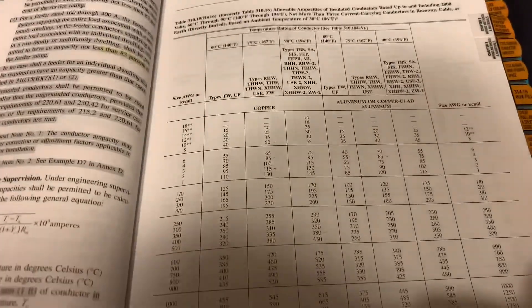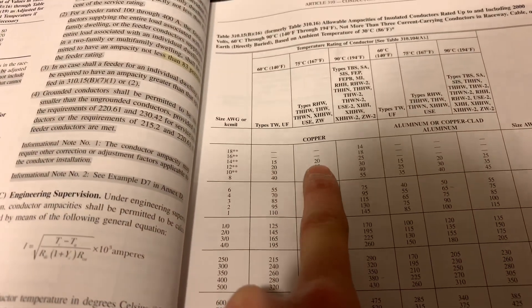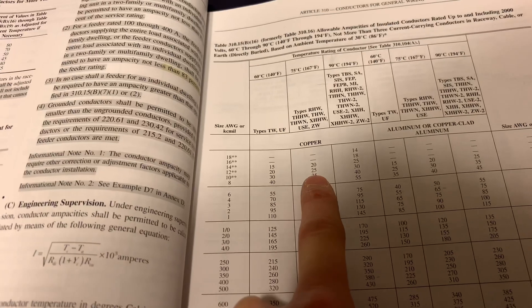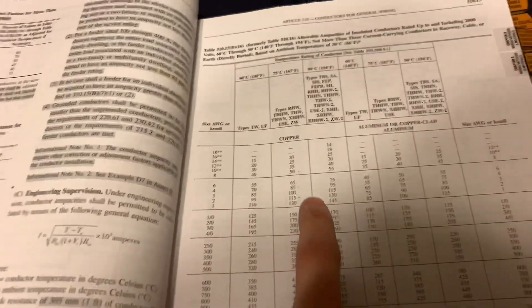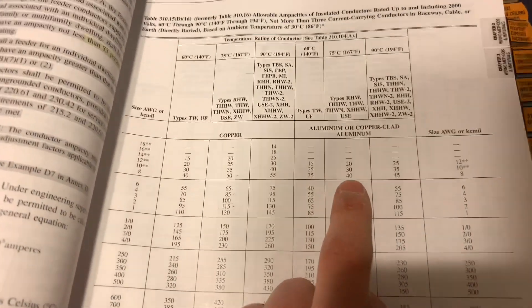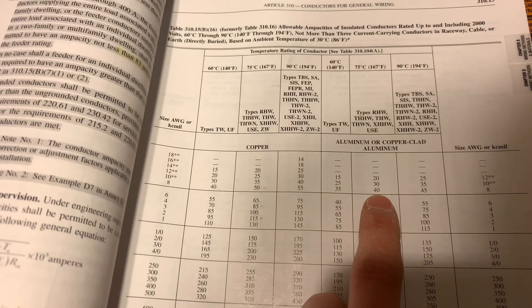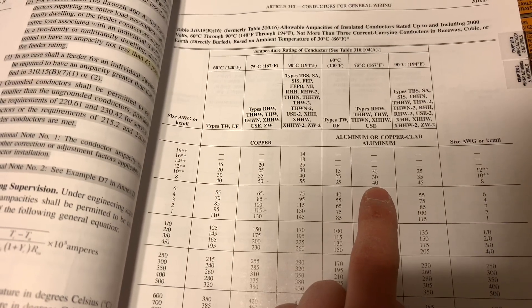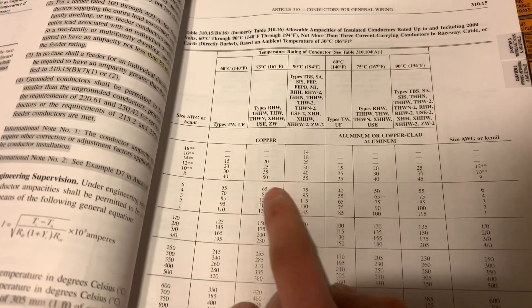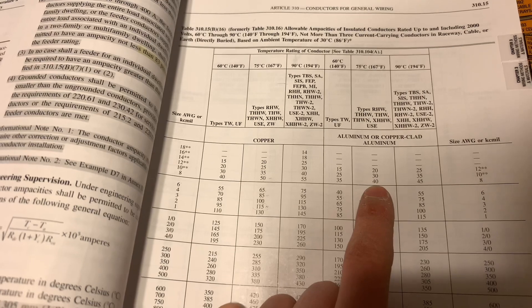Each wire size has its own ampacity. Looking at the table: 12-gauge copper is 20 amps, 10-gauge is 30 amps, and 8-gauge copper is 50 amps, and so on. As for aluminum — it usually has a lower ampacity, so if you're using aluminum you typically have to upsize to match the copper rating. For example, number 8 copper is rated for 50 amps, while number 8 aluminum is only rated for 40 amps.